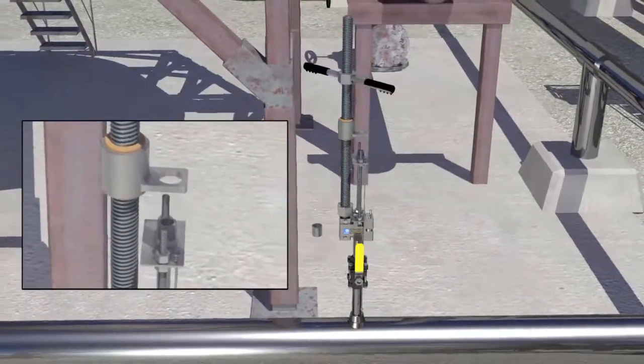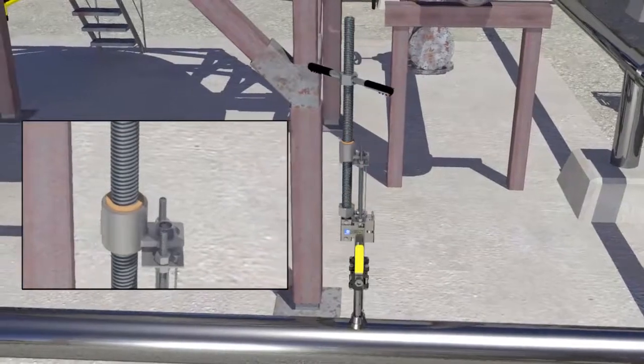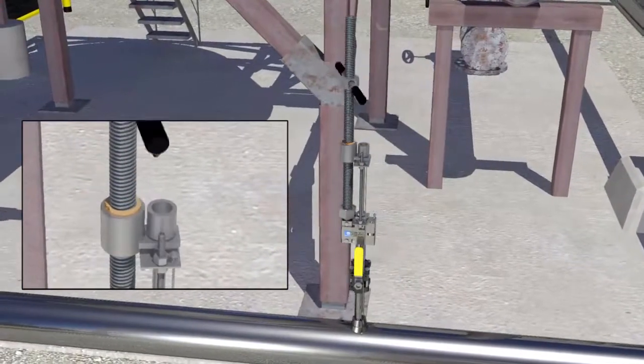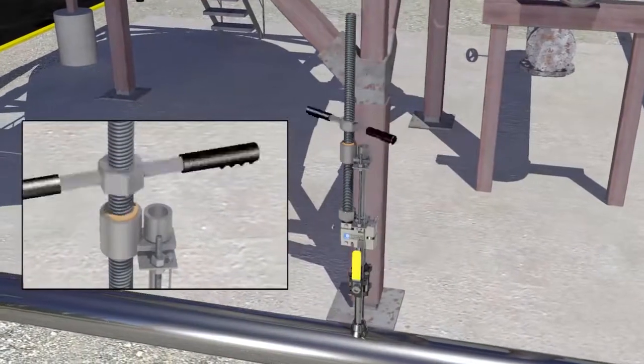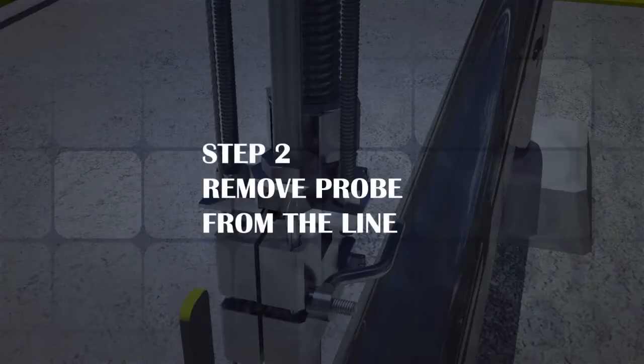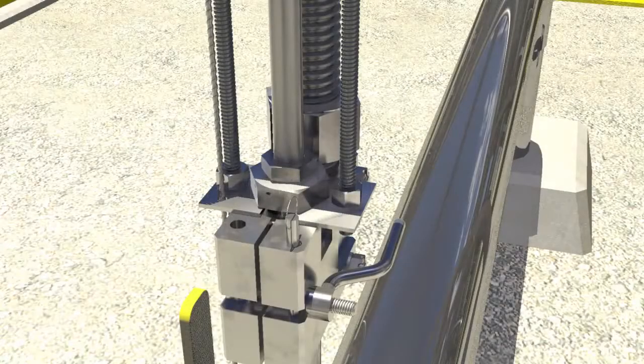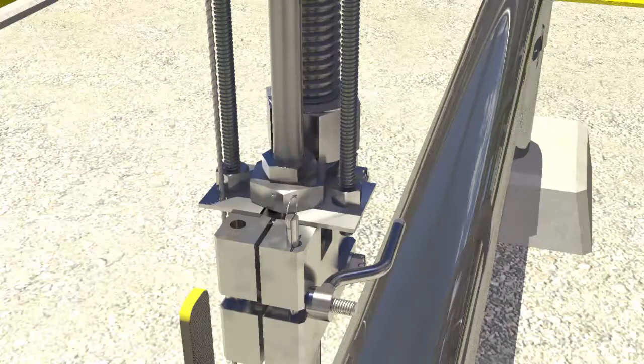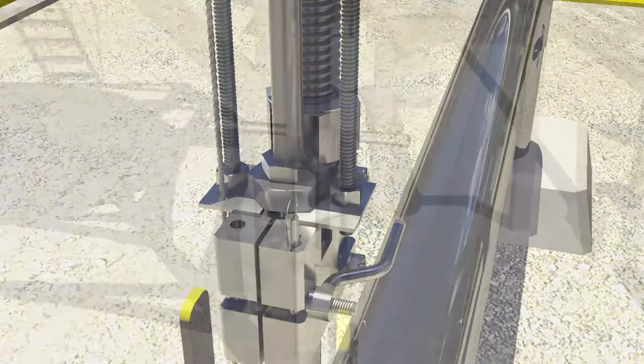Install the thrust coupling over the 1-inch NPT connector threads. Install the coupling fitting on the connector or the adapter. Rotate the handle until it rests just above the thrust coupling. Step 2. Remove probe from the line. Loosen the 1-inch hex locking nut until it can be turned freely. Carefully loosen the 1.5-inch hex stuffing nut until the probe can be retracted smoothly, but no more than one full turn. Should leakage occur around the 1.5-inch hex stuffing nut, then tighten as necessary.